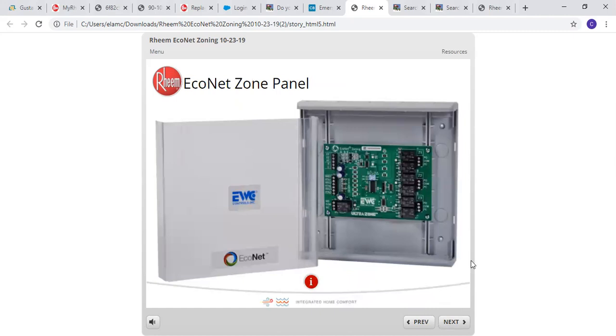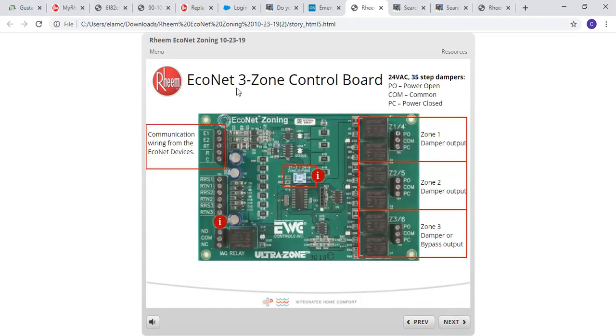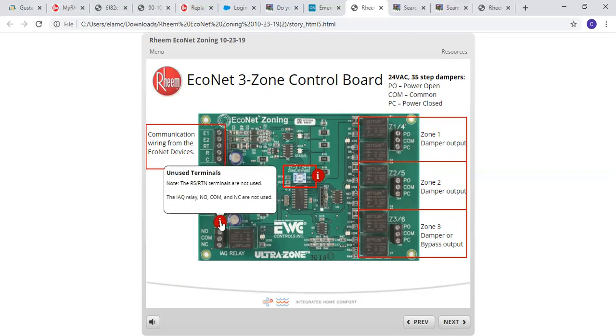Rheem has actually coordinated with EWC Controls to design their zone boards and their dampers. So you will have to use the dedicated Rheem Econet EWC control board. This is a close-up picture of the zone board. You have options for 3 zones on this board. I'll go over the different sections here. Over on the left-hand side, you see the E1, E2, and R and C. That's going to be your Econet communication wires. Down towards the bottom left are unused terminals.